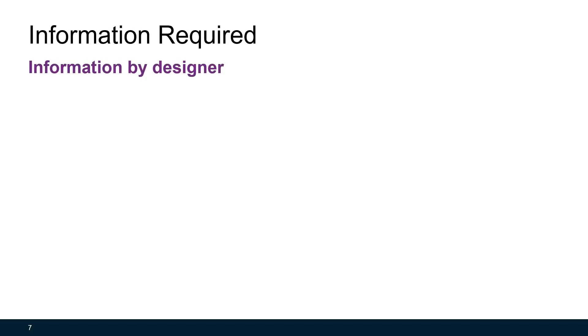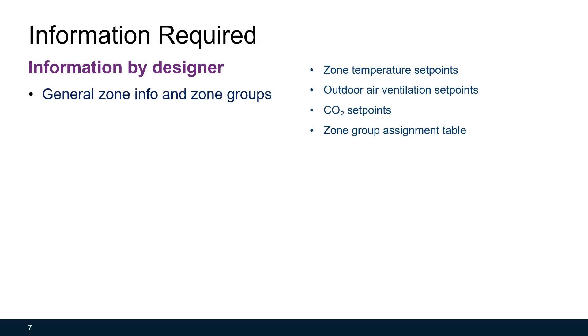To design control sequences for an HVAC system, you first need some information from the HVAC system designer. You need general zone information and zone group information such as zone temperature set points, outdoor air ventilation set points, CO2 set points, and zone group assignment tables.